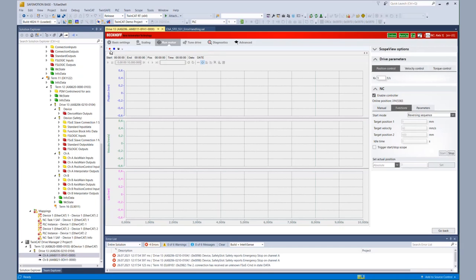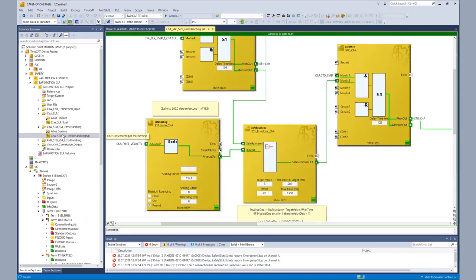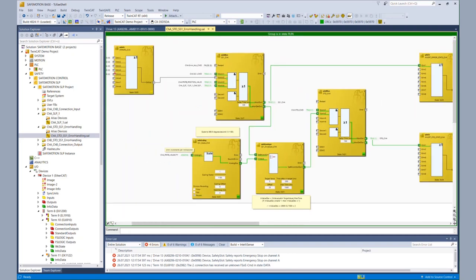We can start to run the motor. We go to the drive manager for Channel A, go to Run Motor, enable our controller and acknowledge the existing error on the axis. We parameterize our reverse sequence — we want to go at 60 millimeters per second with a target position of 600 millimeters. We take a quick look at the scope to confirm signals are changing, then we go back to our safety application, enable online values, and issue the SS1 command. We see the original SS1 signal is gone and the envelope monitoring is working — after the monitoring time the output goes to false and the safety function works as expected.